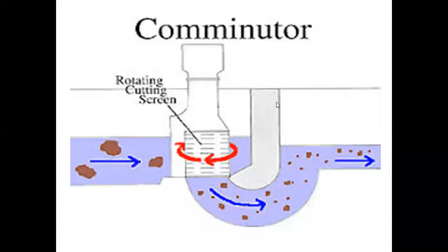As I told you, every unit operation is generating a solid waste, and we are supposed to provide treatment to the solid waste later on separately. So here, if we cut and convert into small pieces, it will flow along with water and will be used by the microorganisms as food in a further biological treatment process. This is the first thing. And there is no need to make a separate arrangement for the collection and degradation of suspended particles present in sewage.